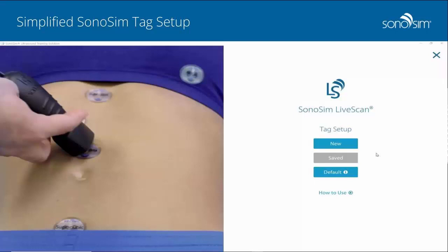One of the critical pieces is that when the product is shipped, it's assuming that all of the internal anatomy has been modeled on, for us, one of our strategic partners. We use SimMan. So we assume that the tags go on SimMan, but they could go on a person with similar body morphology and it'll work fine.